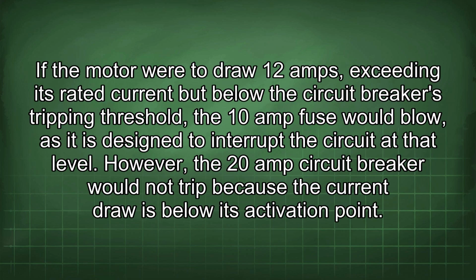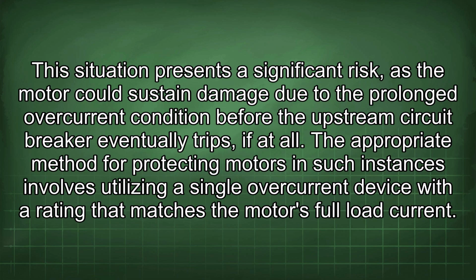If the motor were to draw 12 amps, exceeding its rated current but below the circuit breaker's tripping threshold, the 10-amp fuse would blow, as it is designed to interrupt the circuit at that level. However, the 20-amp circuit breaker would not trip because the current draw is below its activation point. This situation presents a significant risk, as the motor could sustain damage due to the prolonged overcurrent condition before the upstream circuit breaker eventually tripped, if at all.